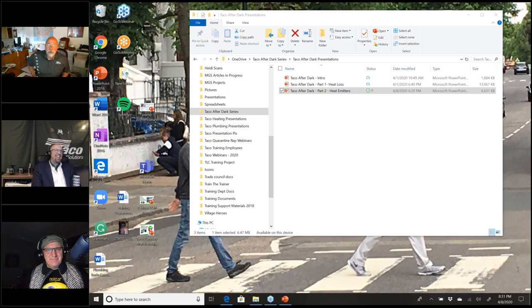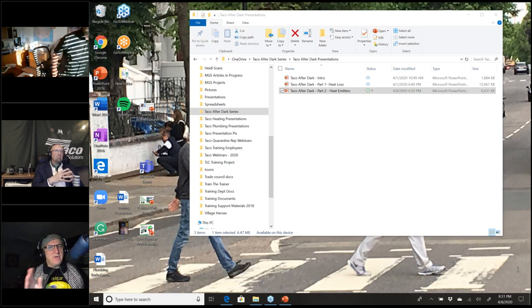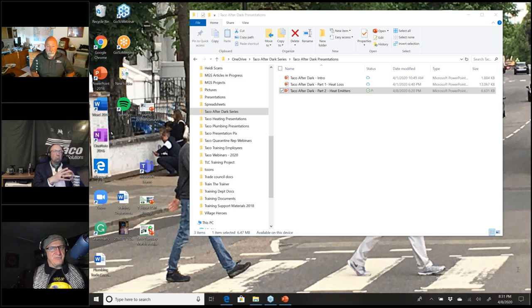And watch out, run. With radiant systems, do you believe in introducing a buffer tank? Yeah, that was one of the things we were kind of foreshadowing with micro zones. When you have a lot of micro zones, and the load of the smallest zone is smaller than the lowest BTU output of your modulating condensing boiler, okay? If the load of the smallest zone is lower than the lowest firing rate of the boiler, a buffer tank's a damn good idea. You're basically adding mass to reduce, if not eliminate, the likelihood of short cycling. In one of our later sessions, we're going to talk about how to size those tanks.